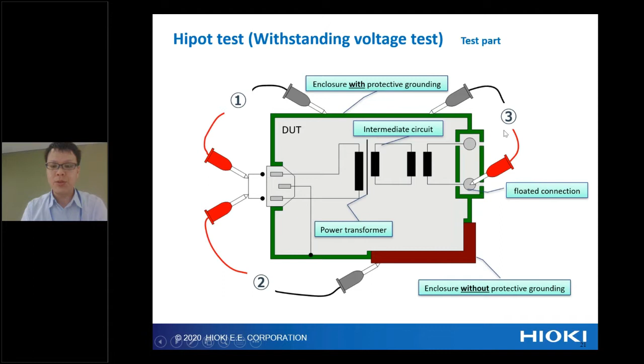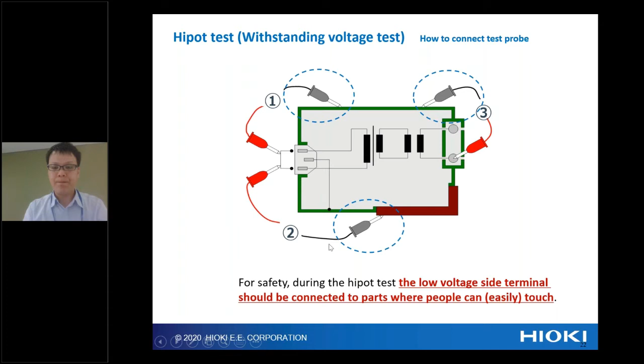For safety, during the Hipot test, the low voltage side terminal should be connected to the parts that people can touch. This is because, as you can understand, the lead probe applies high voltage. That's why, for safety, this connection is safer than the reverse connection.